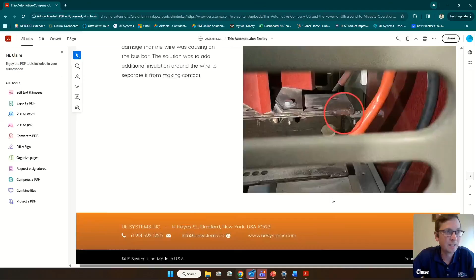It was actually touching basically the bus bar area in the back. Zooming in a little bit, you could see these plates are actually getting welded together because that wire was touching this area. So the wire was giving off mechanical vibration, sound waves embedded inside the electrode, because it was vibrating and touching the metal bus bar there, also creating essentially an arc and tracking. So it's sitting there melting this metal plate inside this electrical transformer, and this was a 13.8 kV scenario.